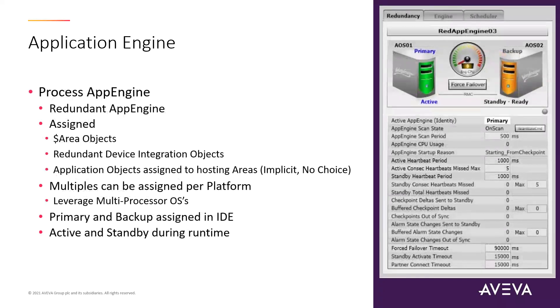The process engine is a redundant engine — that's where we assign our areas, our redundant device integration objects which do care about whether we're getting data to and from the device, and our application objects. Application objects are assigned to areas, and when an area is put on the engine, all application objects assigned to that area are assigned to that engine. We can have multiple engines assigned per platform, and having multiple engines allows that platform to leverage multi-processor operating systems.